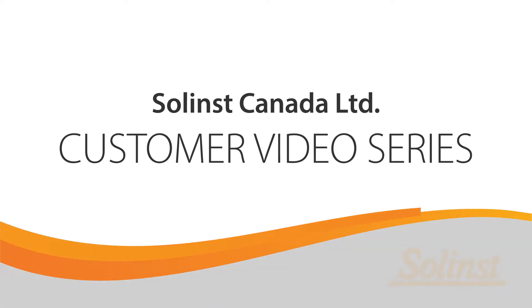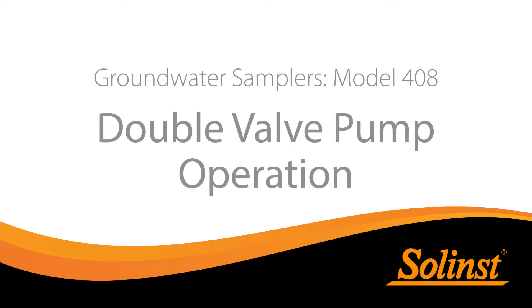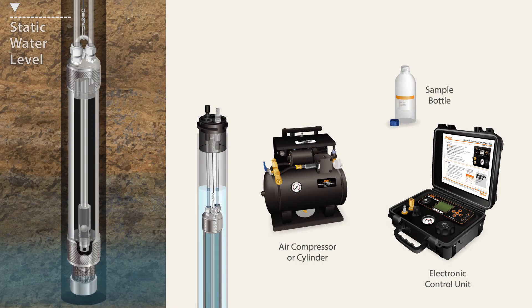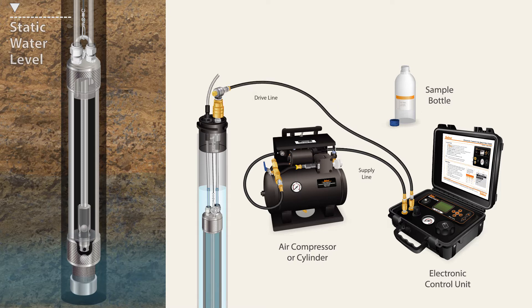Welcome back to Solinst's customer video series. The focus of this video is double valve pump operation. When setting up a double valve pump using a Solinst wellhead, first connect the air source supply line to the electronic control unit. Then connect the drive line from the control unit to the fitting on the wellhead. The sample line connects to the other fitting on the wellhead.